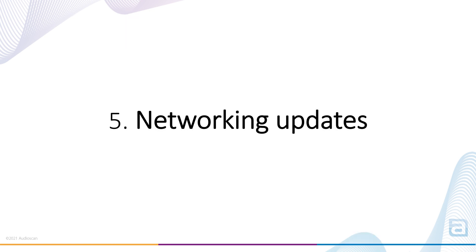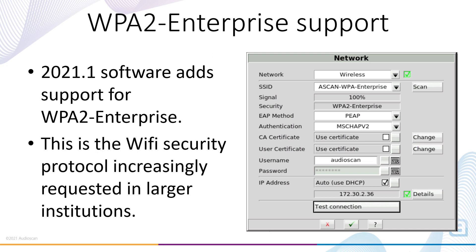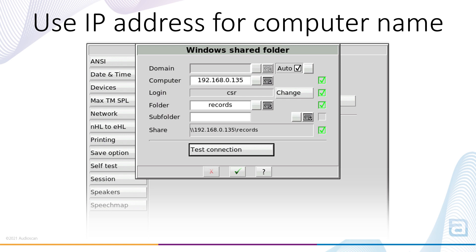Networking updates. The first network change will be of particular interest to IT professionals in larger institutions: the Verifit 2 has now added WPA2 Enterprise to the list of available Wi-Fi security schemes that are supported. This is an important change with the increasing usage of wireless connections in hospitals and other high-security networks. The second change is a small tweak providing increased convenience for anybody who sets up a Windows shared folder for print-to-file or session saving. Previously, setup required entering the computer name where the target folder resides; this can now be substituted with the IP address of the PC, allowing for a faster, more hassle-free setup and is much more reliable on a wider variety of network configurations.